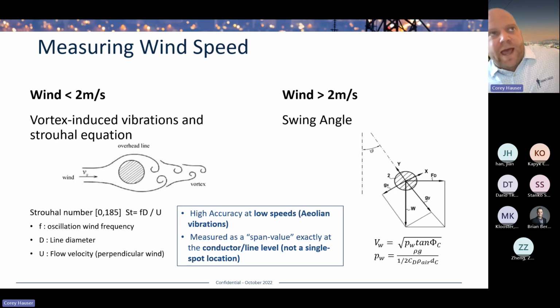Here's a quick look at how we measure wind. Like I said, it's vibration based. At less than 2 meters per second, we measure the turbulent vibrations that occur as wind passes over the line, the aeolian vibrations. Once we pass that 2 meters per second threshold, we move into a swing angle measurement, essentially measuring the force needed to displace the conductor. This happens automatically, without any need on your part, switching between these two methodologies depending on wind speed.